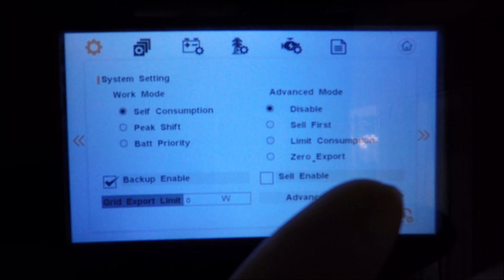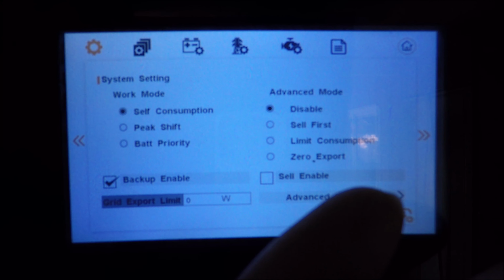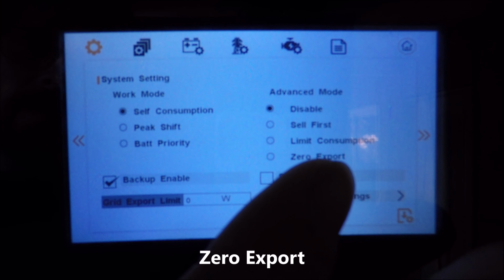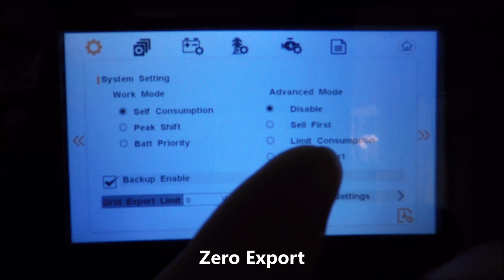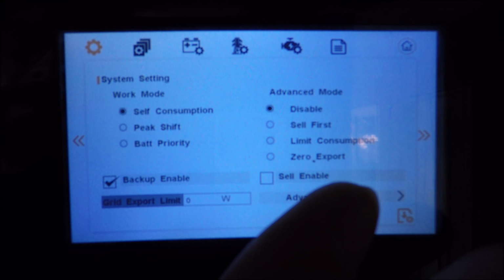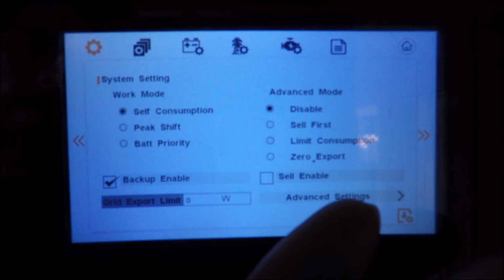If you're selling to the grid, check sell enabled if you're using limit consumption. If not, uncheck it, and that will override the grid export limit. You can use limit consumption with net metering and grid sell. The last one is zero export. If you select zero export, the inverter will work to ensure that no power, no matter what other configuration settings you have, is sold back to the grid.